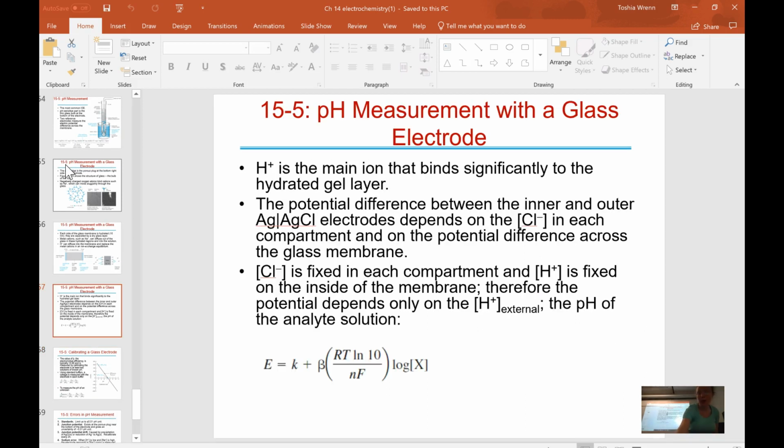Which means you're going to have a diffusion coefficient associated with your pH electrode, and it's going to depend on your electrode, on the day that you're using the electrode, what the electrode has been stored in, and what solution you're submerging the electrode into. So that's why you have to calibrate your pH electrodes. You have to account for these discrepancies that are created because you're working with a hydrated glass sphere.